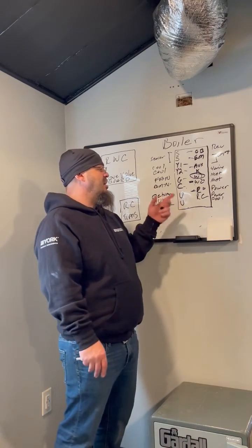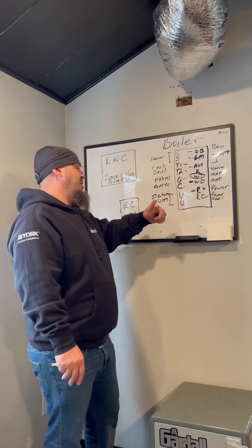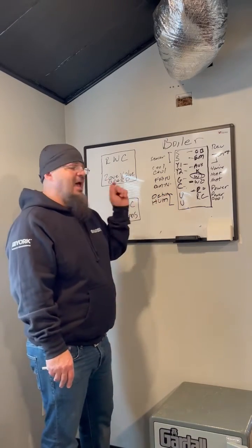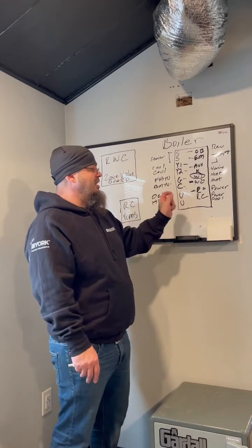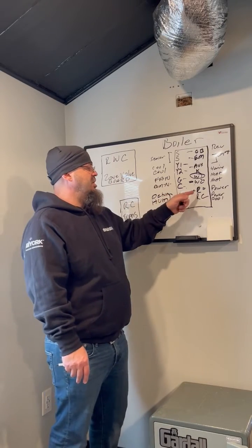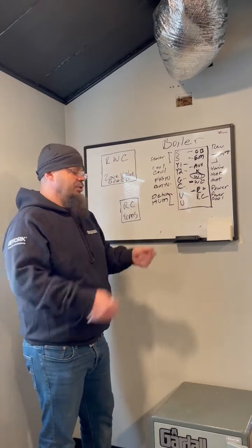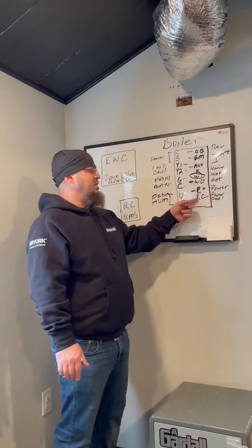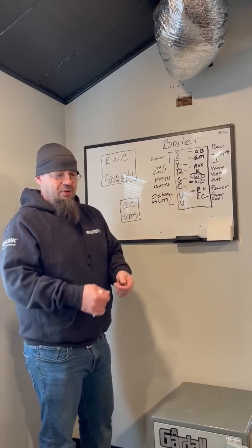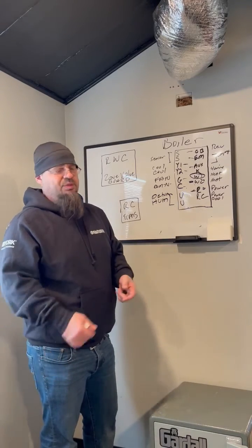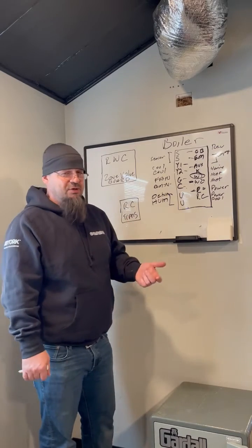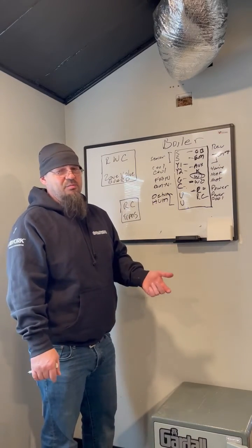The number one thing that you don't want to do with an HVAC thermostat is touch R and C together and have exposed wires. In this case, all you have to worry about is exposed wires. Touching R and W, your 2 wires, together is not going to cause any kind of short in this particular type of system. All it's going to do is spark a little bit sometimes or not, and it's going to make the relay in the boiler chatter, which isn't great for it, but it's not going to break anything immediately.